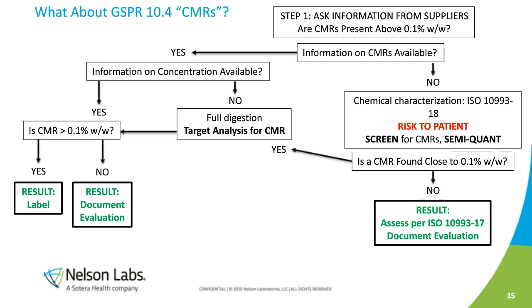And if there's any CMR found that can leave the device at concentrations that would be anywhere close to 0.1% by weight, then we reflex from there and say, okay, there might be a CMR above 0.1% by weight, and additional work might be necessary to really determine if it's over that threshold. But more often than not, what we find is that even when we extract exhaustively, there aren't any CMRs that we can find that have left device materials.